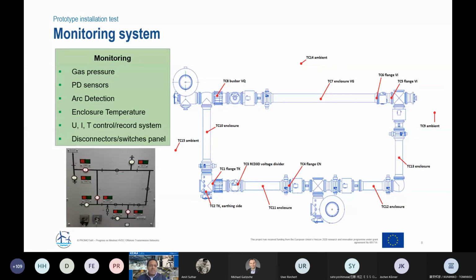Just a few words about the monitoring system. Of course, we have used lots of monitoring, most of them from the manufacturer, also from our side. We do measurements of voltage and current and record them. Here you see on the right side the measurement of the surface temperature of the enclosure. We have put 15 thermocouples at the locations which we thought would be hotspots. And of course, there is also monitoring of ambient temperature, so we place thermocouples in the vicinity of the GIS to control the room temperature too.